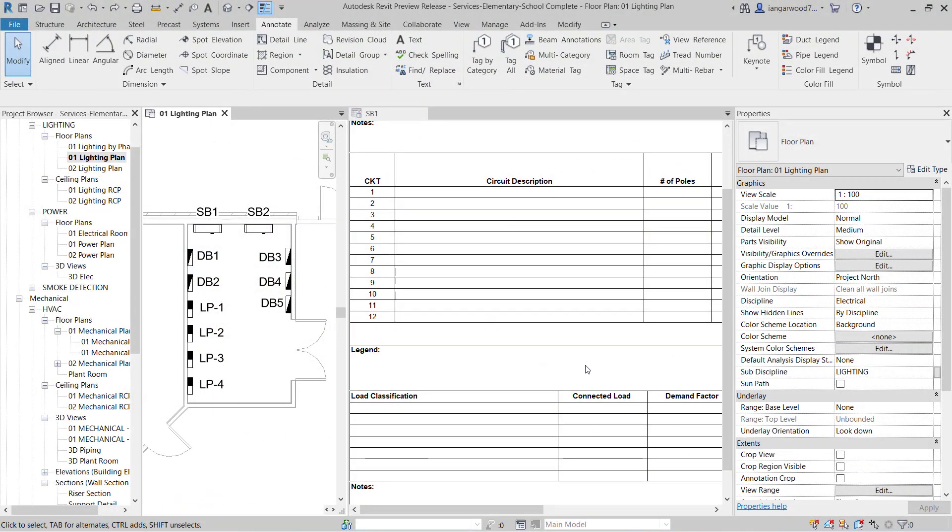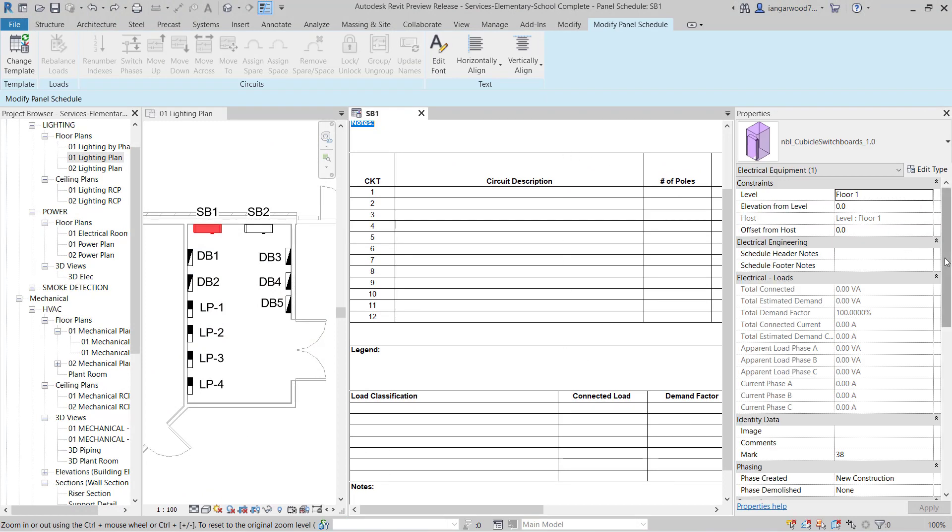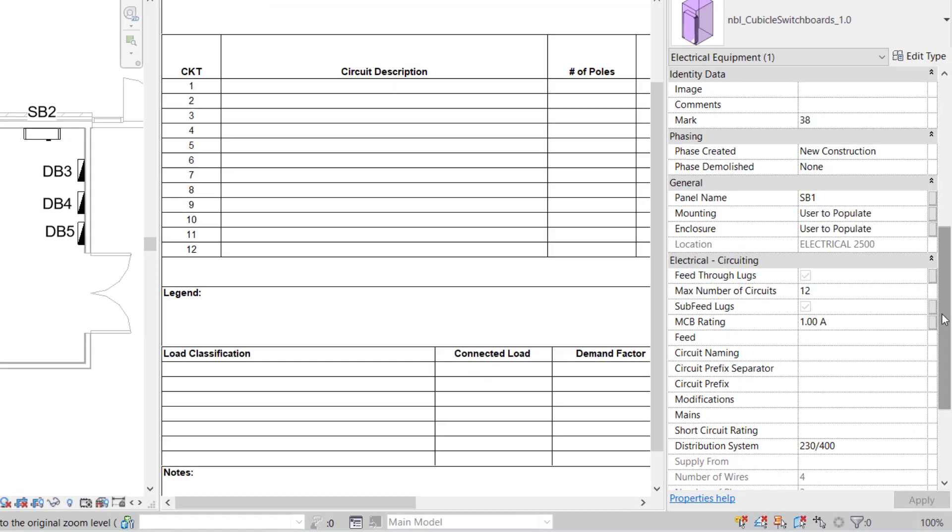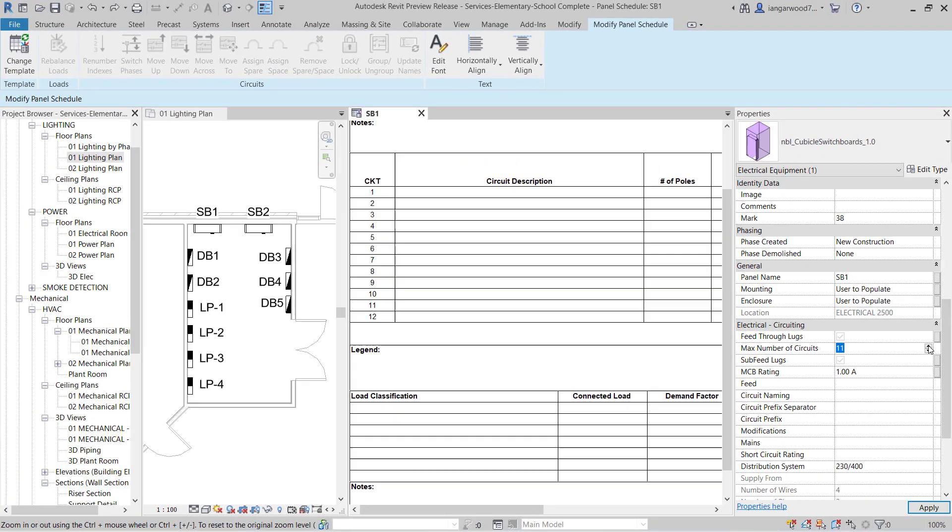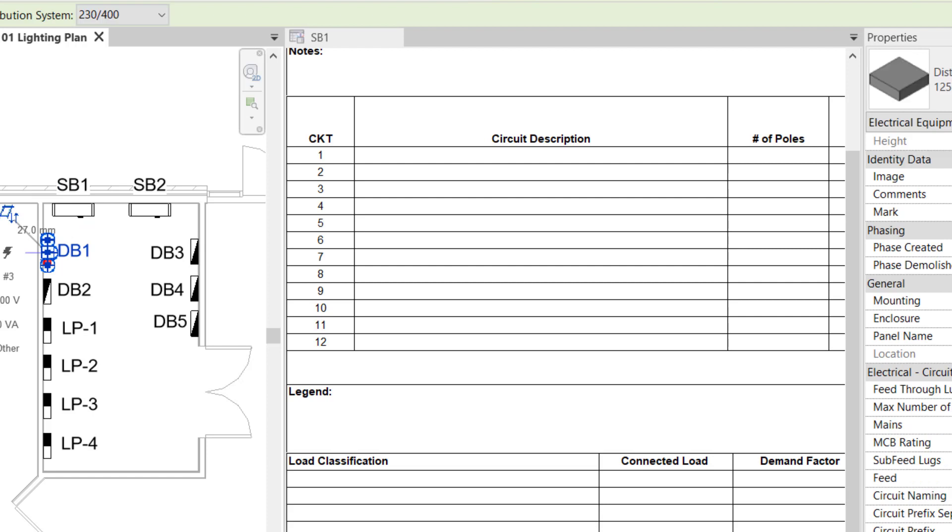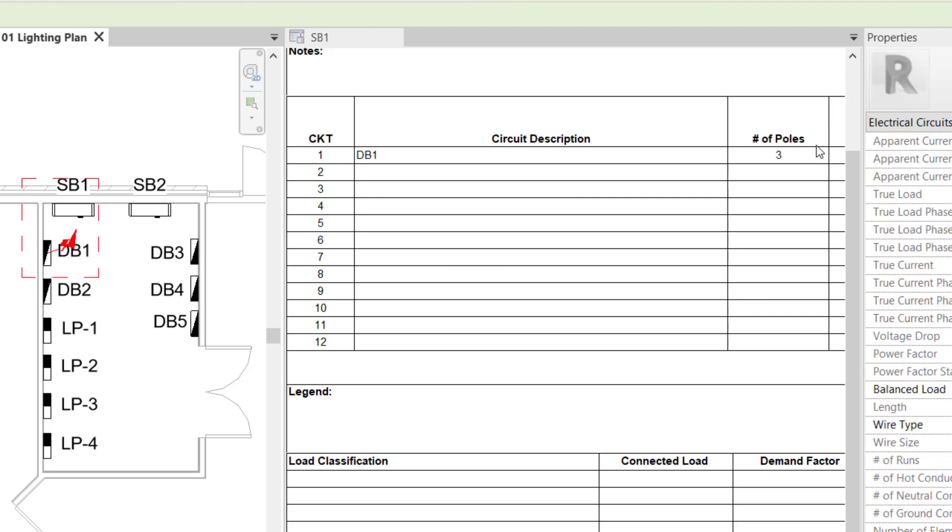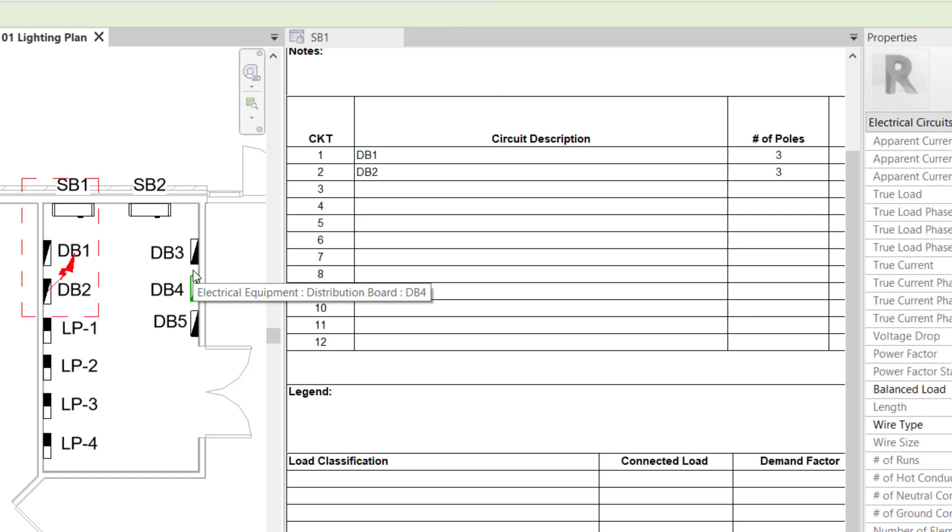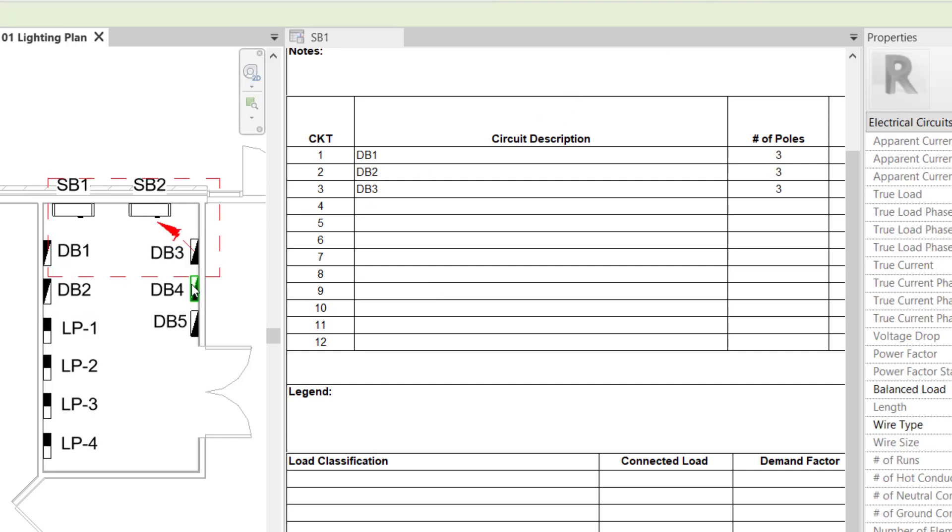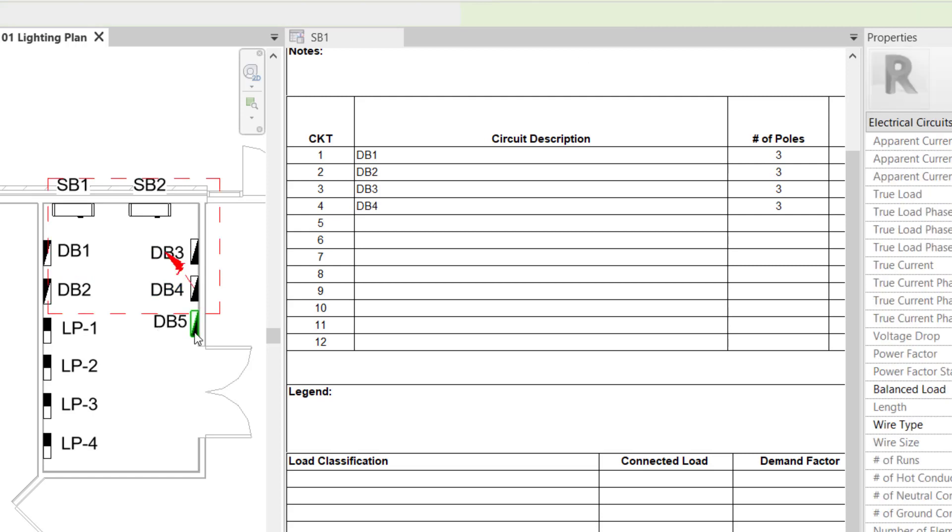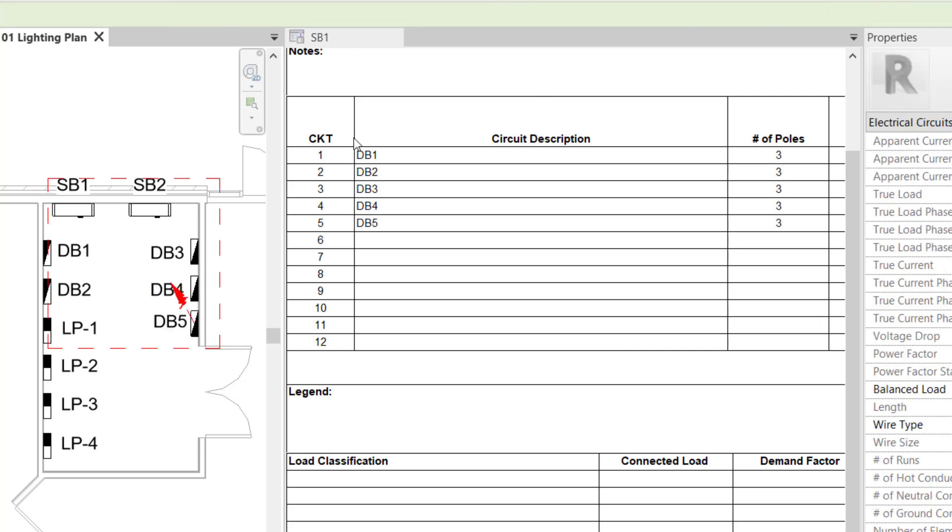This has been addressed for switchboards in Revit MEP 2021 where the maximum number of single pole breakers parameter has been replaced with maximum number of circuits, giving a truer reflection of the number of occupied and available slots. Put into practice, even though the new parameter of maximum number of available circuits is set at 12, the same as the previous number of maximum single pole breakers, you can see that the switchboard's capacity is not exceeded after connecting four three-phase panels, giving a more accurate account of the remaining available capacity. In this example I'm connecting five distribution boards to a switchboard and will be able to continue adding circuits until the maximum of 12 is reached.